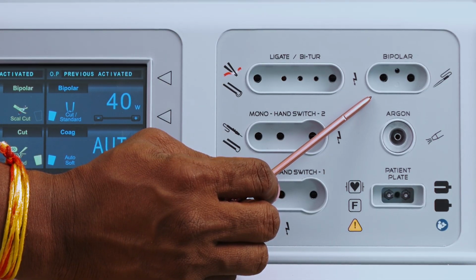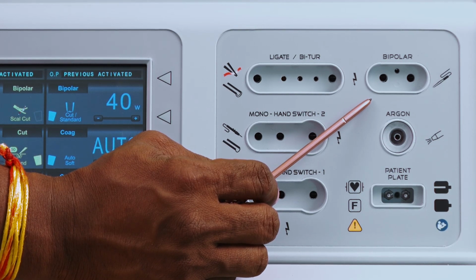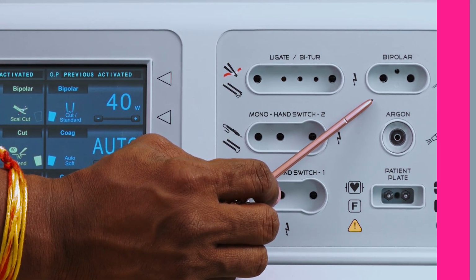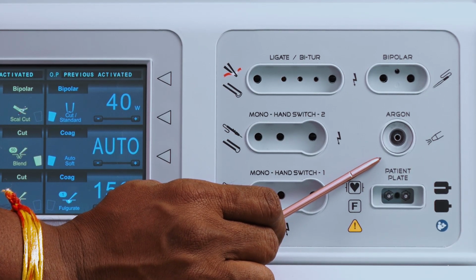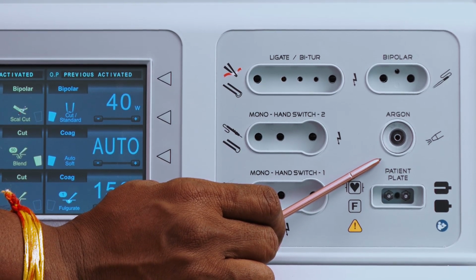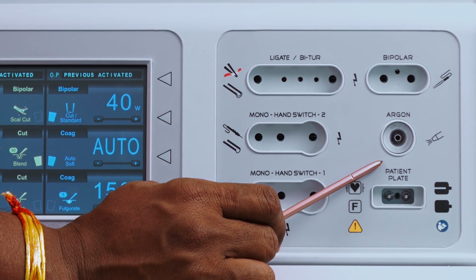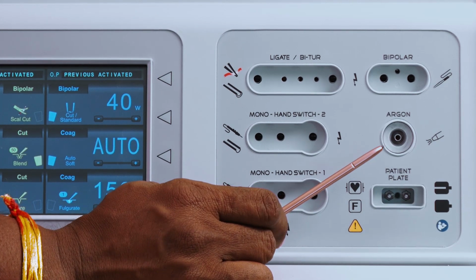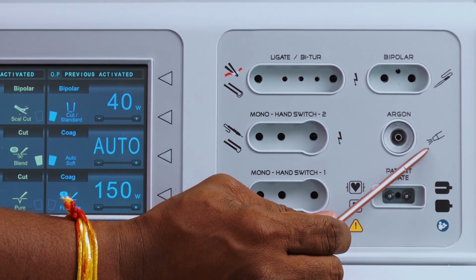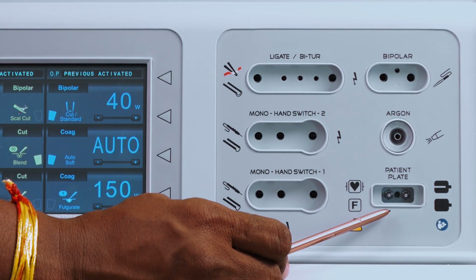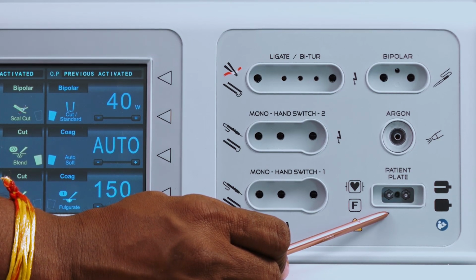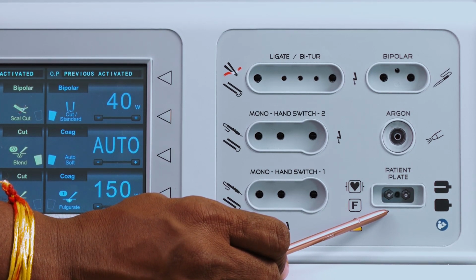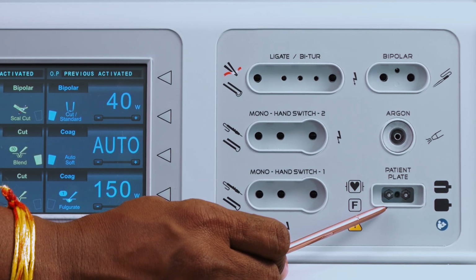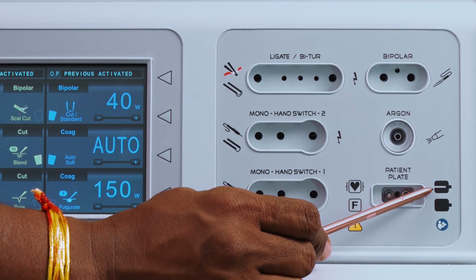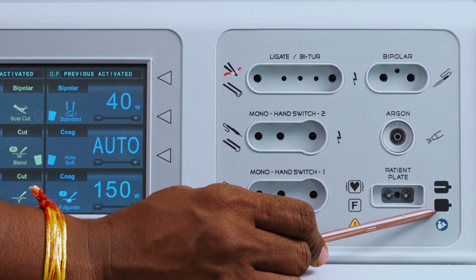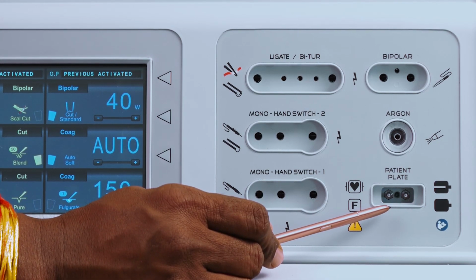This is a standard bipolar receptacle with several modes to facilitate your surgical precision. This is a very unique and innovative port for APC, which is used in specialized and niche surgeries based on argon. You can have a look at this label. This is a very important and integral part of safety for monopolar based surgeries. This patient plate receptacle supports both split and non-split type of patient plate, whether they are disposable or reusable in nature.